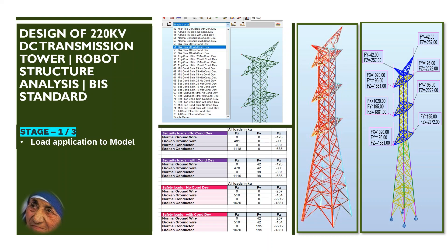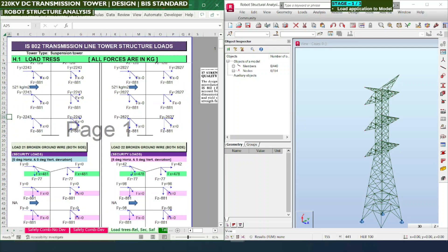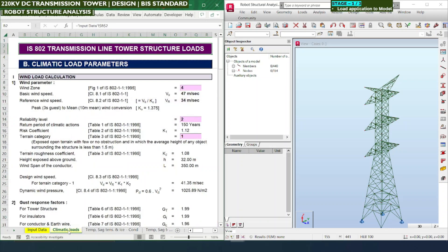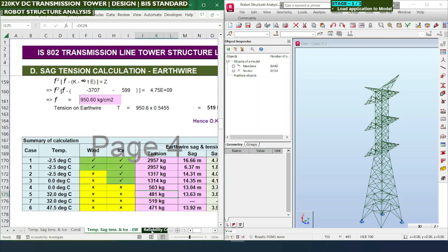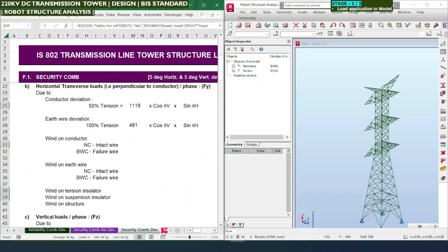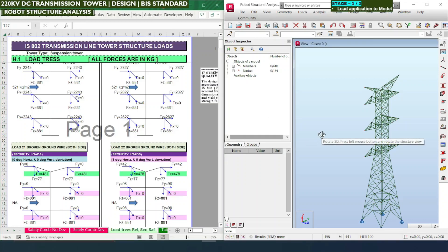Let me go into the model view. On the left-hand side you can see the Excel calculation done in our previous 7-stage video series — starting from electromechanical input, climate loads, temperature, sag tension, calculation for conductor and earth wire, reliability load combinations, and security and safety load combinations. On the right-hand side you can see the Robot Structural model of the 220 kV double circuit transmission line tower.